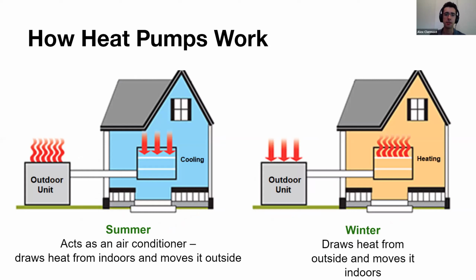Again, here in the building, you have the same system in the summer, which is taking heat from inside and rejecting it outdoors. And in wintertime, you take heat from outside and bring it inside the house. Now you're going to ask me, hey, Alex, does air at 0 degrees Fahrenheit outside have any heat left in it? Well, it does. Unless you're at absolute zero, there's always heat in the air. 0 degrees Fahrenheit is cold for us as humans, but for a refrigerant, it's just another line on the pH diagram that it uses.